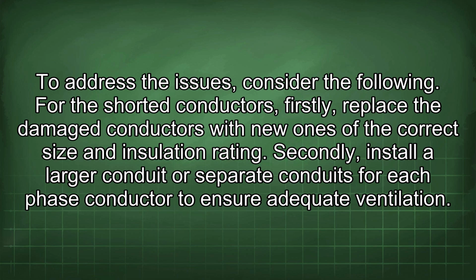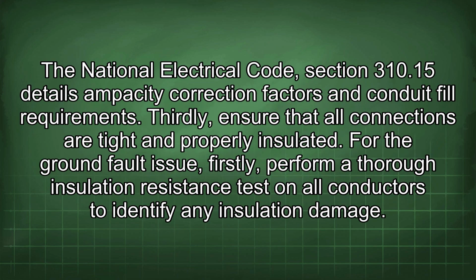For the shorted conductors, firstly, replace the damaged conductors with new ones of the correct size and insulation rating. Secondly, install a larger conduit or separate conduits for each phase conductor to ensure adequate ventilation. The National Electrical Code, Section 310.15 details ampacity correction factors and conduit fill requirements. Thirdly, ensure that all connections are tight and properly insulated.